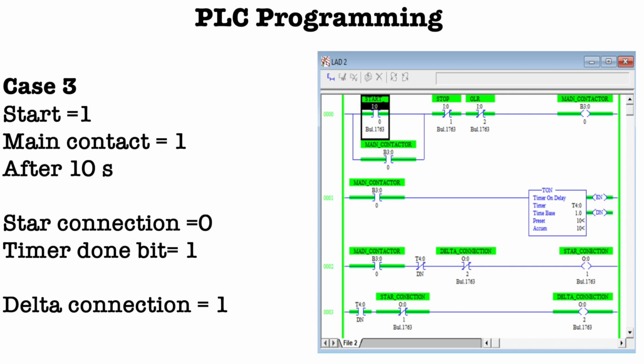you can see when the timer provides the done bit, the fourth rung is getting supply and the third rung doesn't get any supply because the done bit is connected as an NC switch, right? So in the fourth rung you can see when the done bit is high after 10 seconds, my delta connection is on, and because of the interconnection the third rung goes 0 and the star connection goes 0, right?